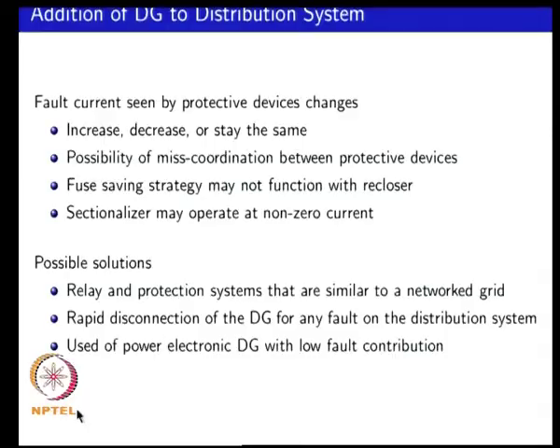We saw that in general, in a distribution system, the fault current levels can actually increase, decrease, or stay the same. If your fault current level changes during the addition of a distributed generator source, then there is a possibility of miscoordination between your upstream and downstream device because of this change in the current level. You cannot uniformly say that the current level is always going to increase at the protection point; it can actually go in all three ways.